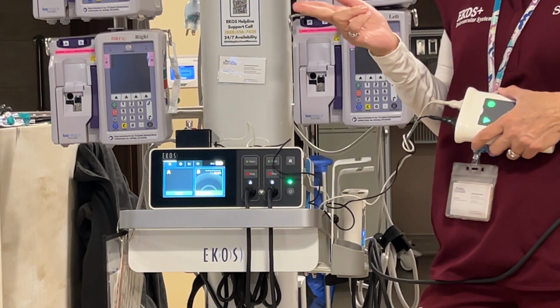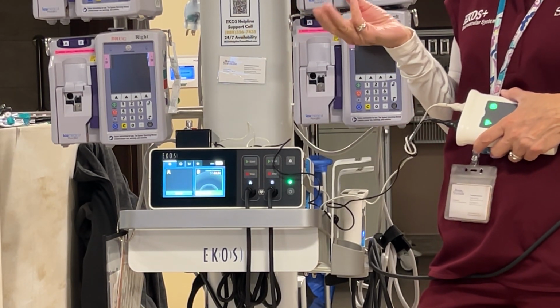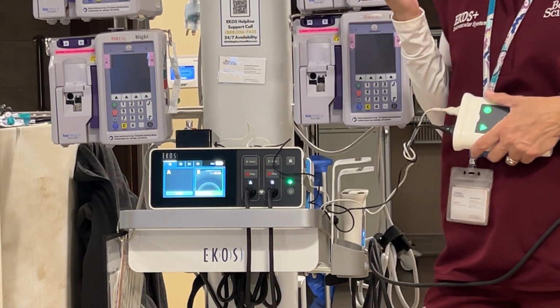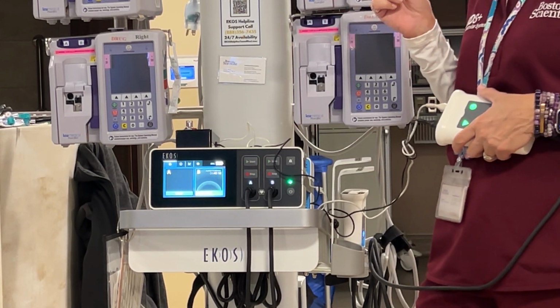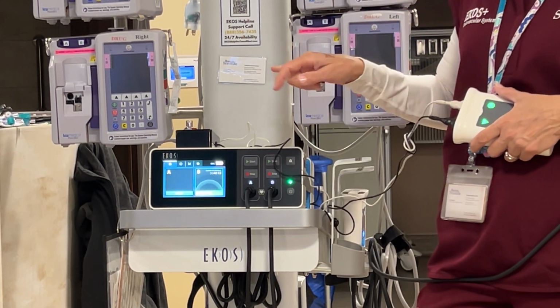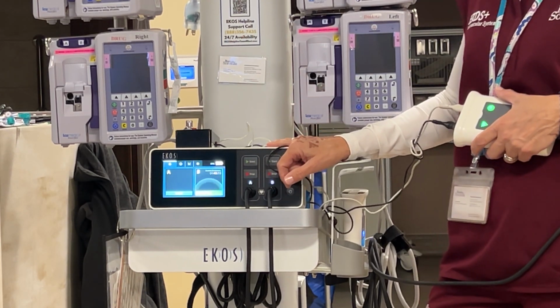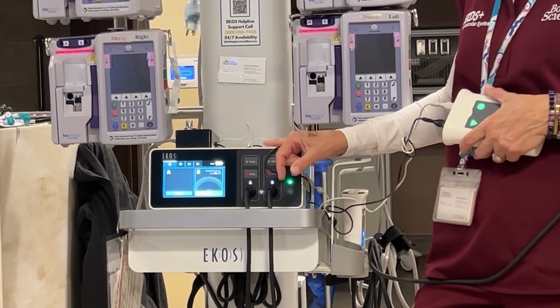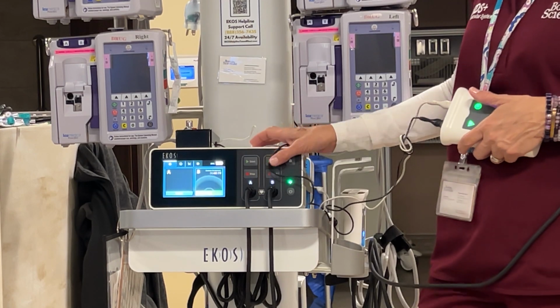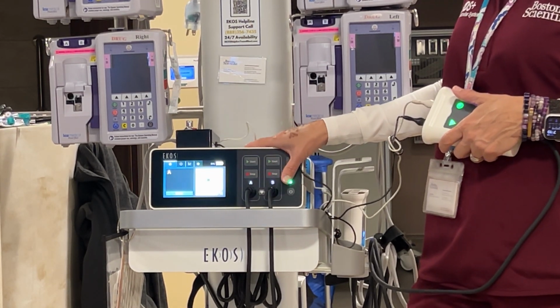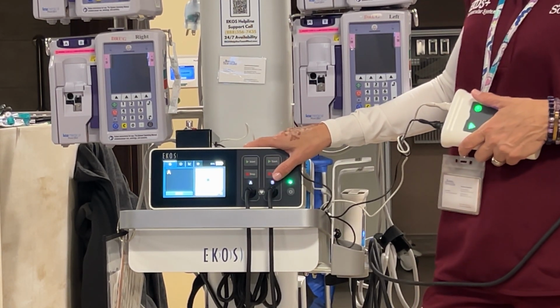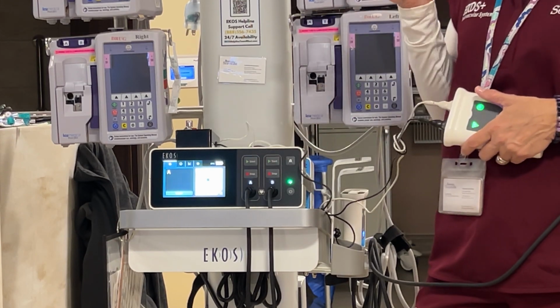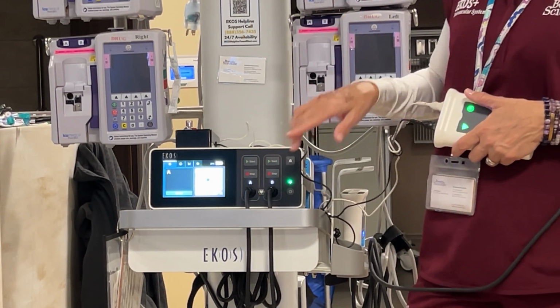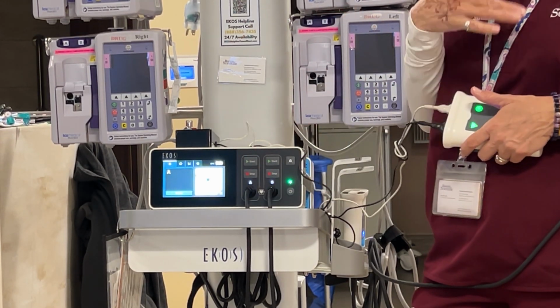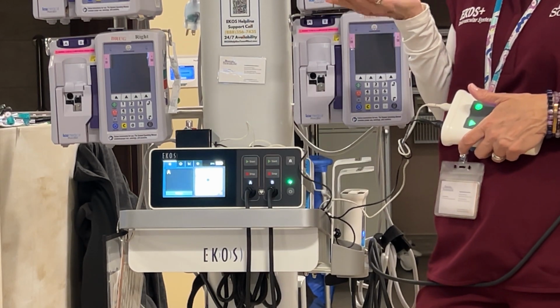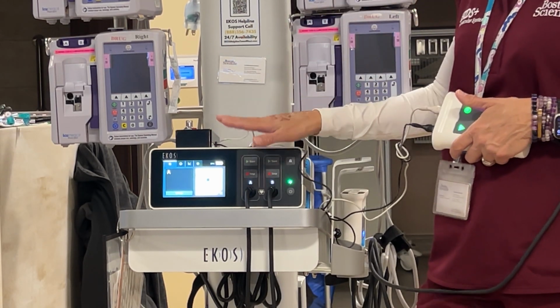Echo, Doppler, duplex ultrasound, and a bladder scanner. Those exams might experience artifact or interference from the ultrasound that we use, if it's a similar or close frequency. In those cases, you would hit stop to pause the ultrasound. In 5 minutes, it will beep to remind you to restart. If you need longer, you can hit the stop button again and reset the 5-minute timer. We're only pausing the ultrasound.